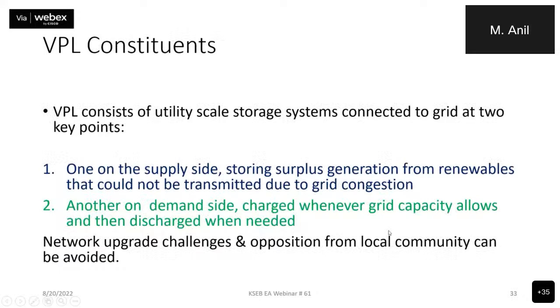So, VPL constituents. VPL consists of utility scale storage systems connected to the grid at two key points. One on the supply side, storing surplus generation from renewables that could not be transmitted due to grid congestion. Another on the demand side, charging whenever grid capacity allows and then discharging when needed. Network upgrade challenges and opposition from the local community can be avoided with this arrangement. So network upgrade means the transmission line capacity has to be enhanced, which is time consuming.